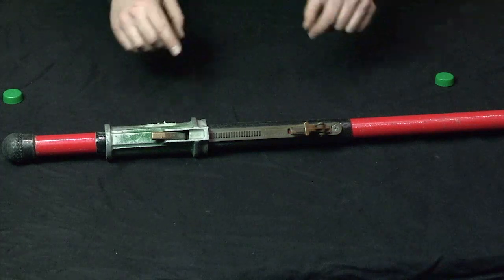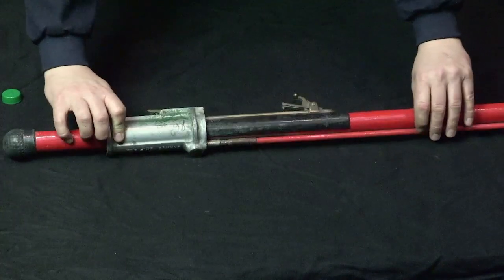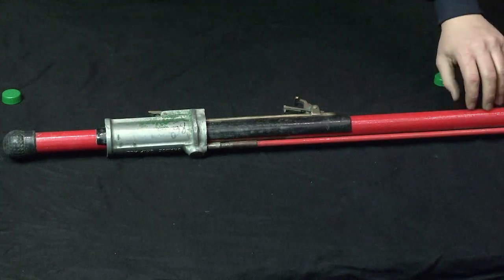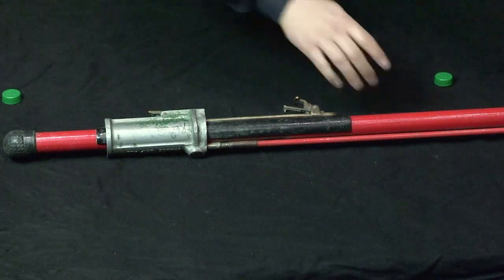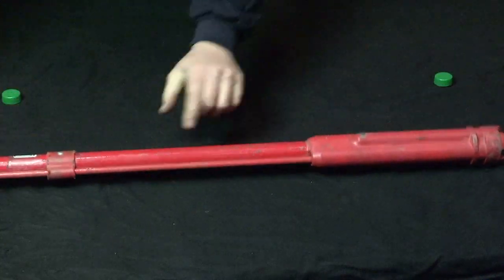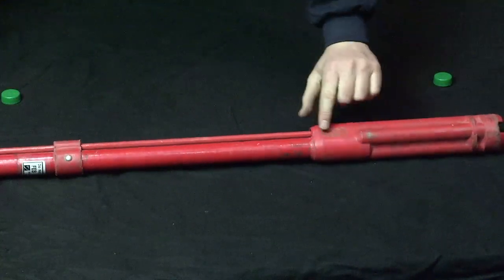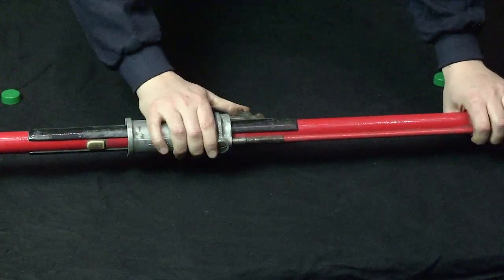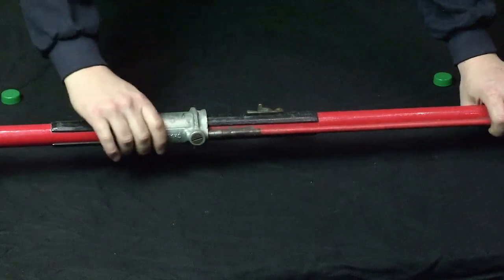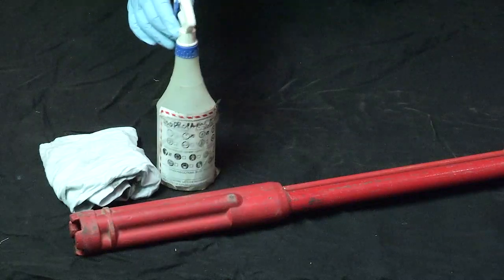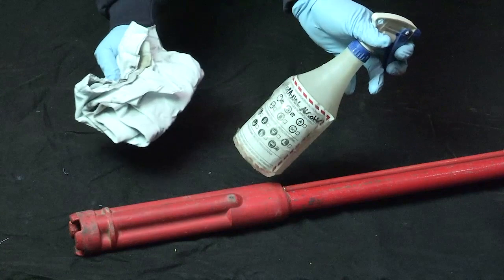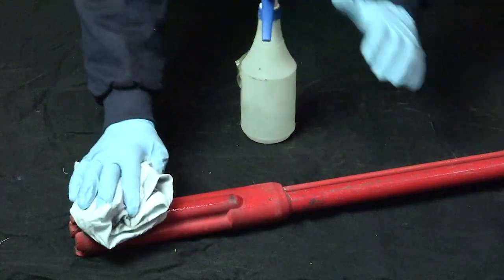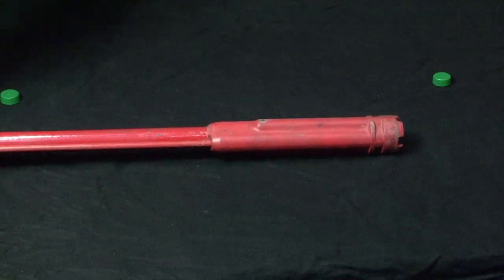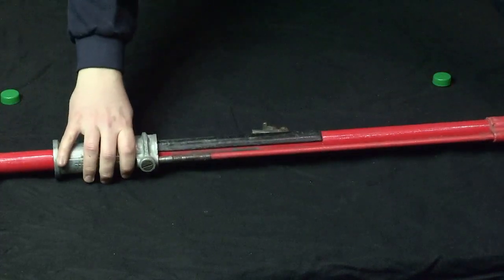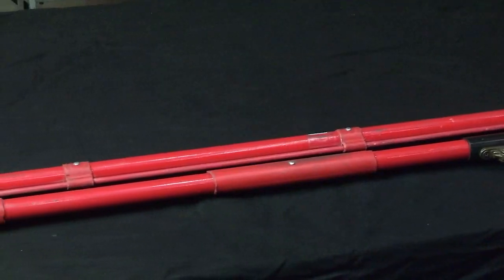Inspect epoxy and fasteners used to bond hardware to the fiberglass. Check the mechanical function to ensure the stick operates smoothly and the latches fasten properly. Check that the switch stick hook has free movement and will retract fully into the stick as required. Lubricate moving metal parts of live line tools as required with approved dry film lubricant. If the stick is dirty, wipe it down with isopropanol. Live line tools must have an unbroken length of fiberglass insulation equal to or greater than the absolute limit of approach for the voltage being worked on.